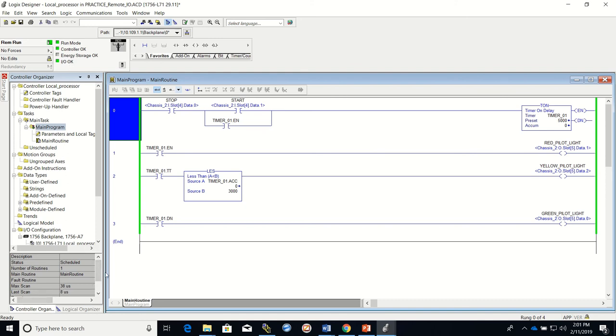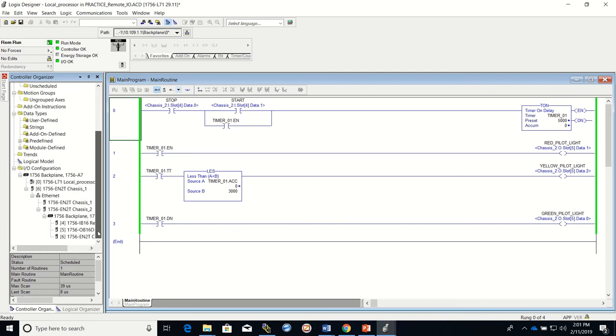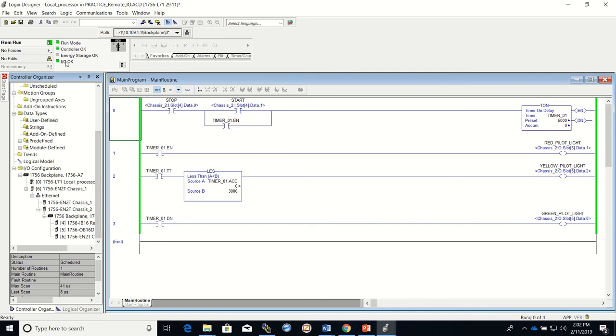You can see up here it's telling me that my IO is okay and I'm not showing any faults, which is a good thing. If you have any little yellow signs — they sort of look like a yield sign — on anything in the tree, that means something is wrong, usually a setting or communication issue. There will be an alarm telling you the general issue and you'll need to fix that before moving on. This one is telling me IO is okay, so we can move forward. That is how you do remote IO with Studio 5000 ControlLogix — I hope that helped.